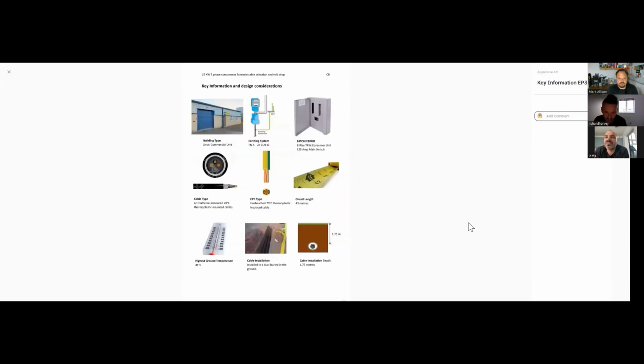So this is the key scenario information, and like we were talking about last week, I always find it easy, out of the scenario or the question, to pull out the more important bits of key information, and then you can consider those in your design. So again, quite simple really, but we've got a little image of the building type, a small commercial unit, a picture of our earthing system, a picture of the three-phase MEM Eaton board, loads of those about, the cable type, a picture of what that's going to look like, your single insulated CPC that we've got to install separately, circuit length, as we've said, 43 metres, highest ground temperature, we're expecting 35 degrees C. And our cable installation, we know that it's going to be inside a duct in the ground at a depth of around 1.75 metres. So all that information is important.